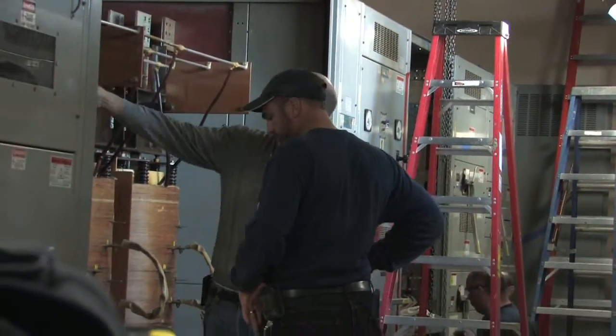It's a 24/7 operation. And once every 5 years, they bring down utility and they want to do a complete inspection of everything. So it was discovered that the insulation on the windings on both transformers came up as a potential problem. There was an abnormal reading. Not a complete failure point, but showing signs, because the beauty of the bank sticking with their program is they had a track record to go back to.